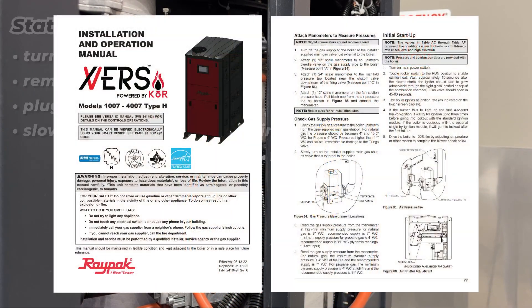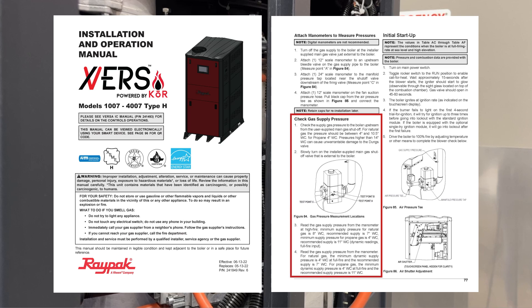Refer to the I&O manual of the unit you are working on for exact gas pressure numbers. If the pressure you are reading is above or below what is stated in the manual, you will need to make adjustments to the regulator or, in some cases, add a regulator that is dedicated to the boiler.